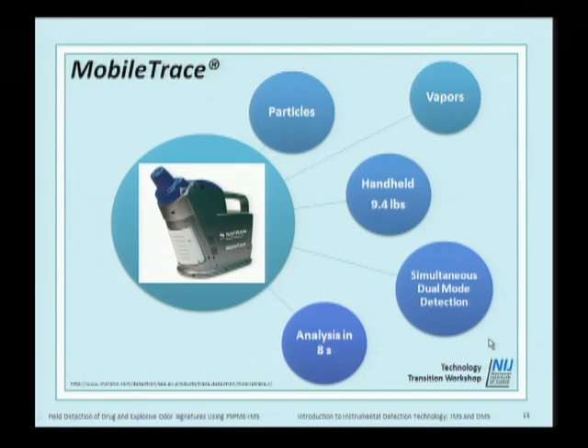The next one is the handheld IMS system from Morpho Detection. It's called the Mobile Trace, and it weighs only 9.4 pounds. It detects both particles and vapors, but you'll see that with particles, you have the nozzle of the desorber that you would have to remove for detection of vapors. But again, there's no pre-concentration like PSPME would provide with this instrument. Again, this is also simultaneous dual mode detection, so we can see our volatile chemical signatures both in the positive and negative mode, which is advantageous. And again, the analysis is done in as little as 8 seconds.